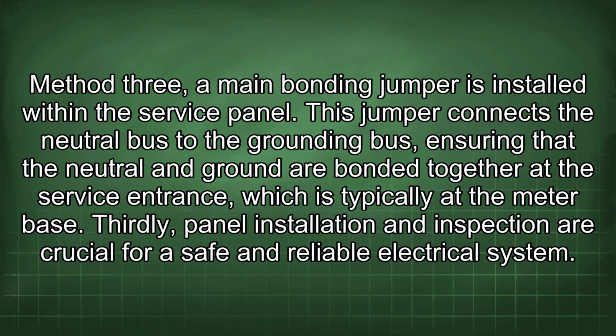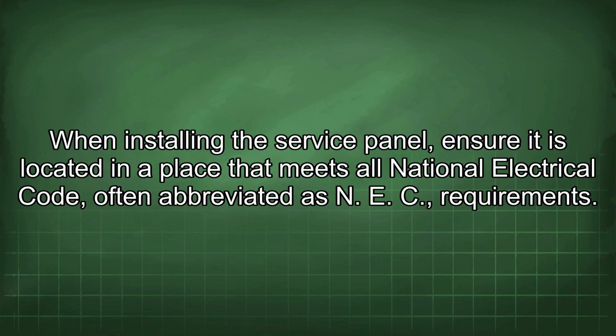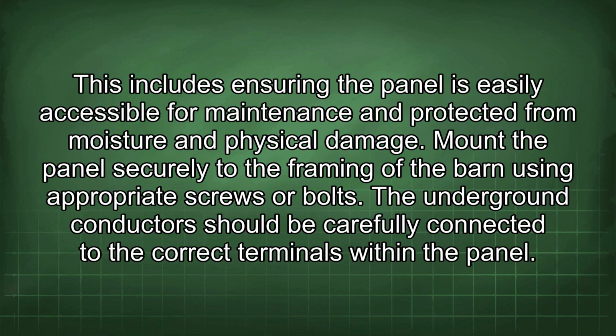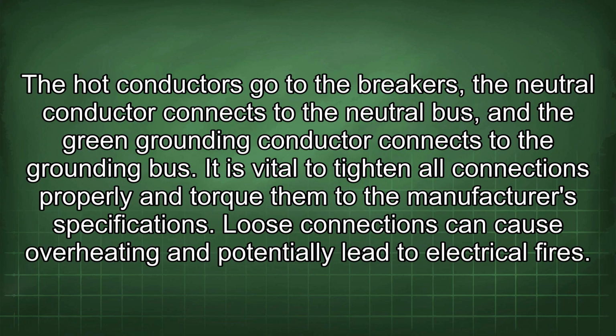Thirdly, panel installation and inspection are crucial for a safe and reliable electrical system. When installing the service panel, ensure it is located in a place that meets all National Electrical Code, often abbreviated as NEC, requirements. This includes ensuring the panel is easily accessible for maintenance and protected from moisture and physical damage. Mount the panel securely to the framing of the barn using appropriate screws or bolts. The underground conductors should be carefully connected to the correct terminals within the panel. The hot conductors go to the breakers, the neutral conductor connects to the neutral bus, and the green grounding conductor connects to the grounding bus. It is vital to tighten all connections properly and torque them to the manufacturer's specifications. Loose connections can cause overheating and potentially lead to electrical fires.